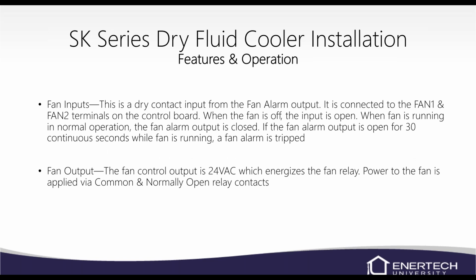Fan inputs, it's a dry contact input from the fan alarm output. And it's connected to the fan 1 and the fan 2 terminals on the control board in the fluid cooler. So basically when the fan is off, input is open. When the fan is running in normal operation, the fan alarm output is closed. If the fan alarm output is open for 30 continuous seconds while fan is running, a fan alarm will trip.